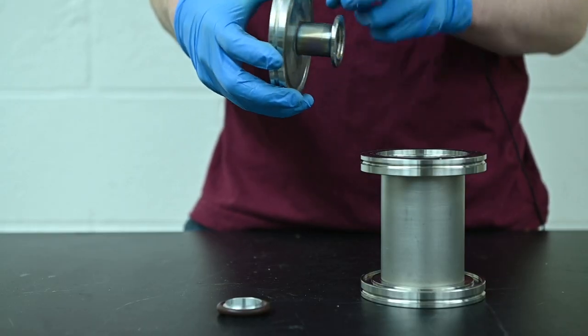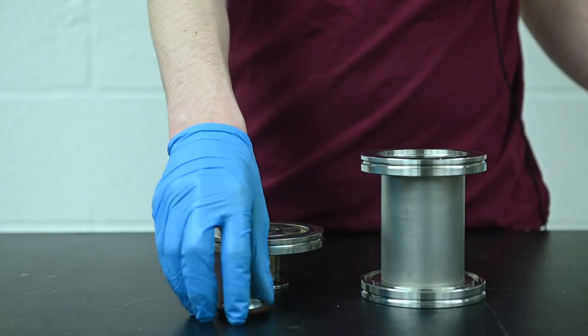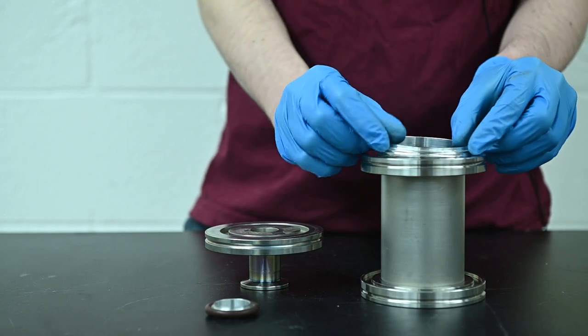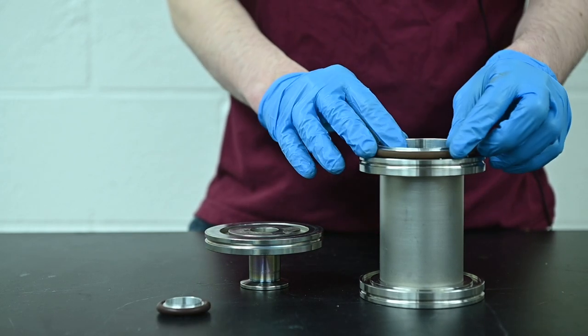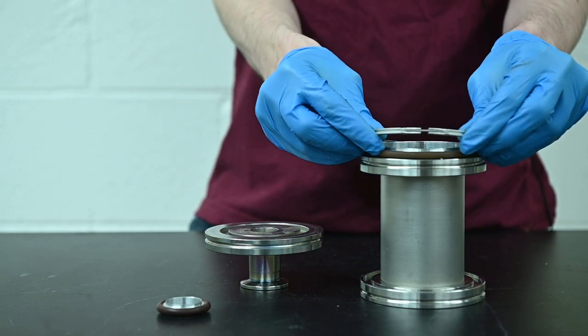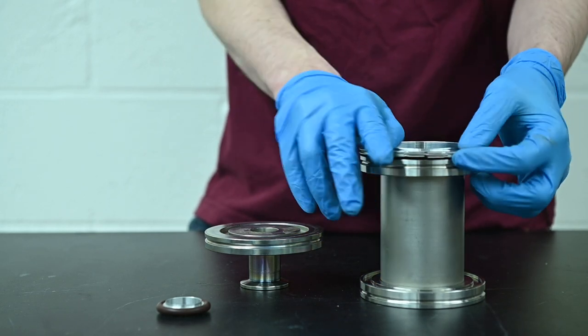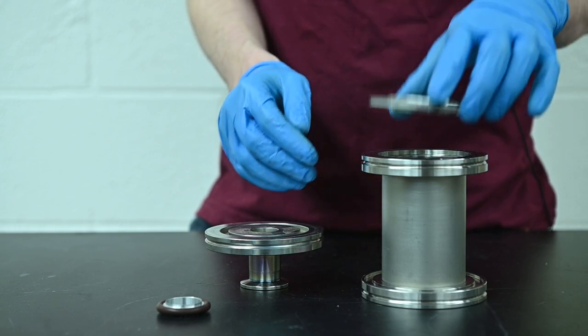For KF sizes larger than 50, the external taper is omitted and an external groove is added to be gripped by C-clamps. In addition to the internal centering ring, an external centering ring may also be added to the O-ring to prevent the O-ring from being extruded if there is overpressure in the system.